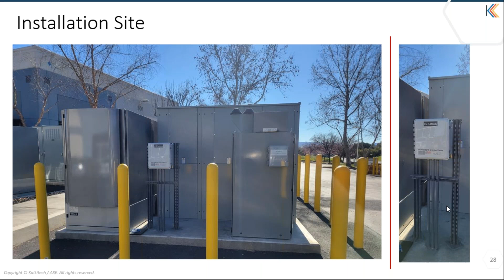So for the steps adopted for installation and maintenance, I'll go through the phases of this project. Since this was the first project done at a PG&E location, we had a detailed process for the data collection. We had to find out which meters would be available downstream, and how the meter connections would happen, whether through TCP or serial, and what the serial port parameters and the TCP networking parameters are. We had to collect all that information. And once the meters were identified, we also collected the IO list of those meters for the Modbus mapping.